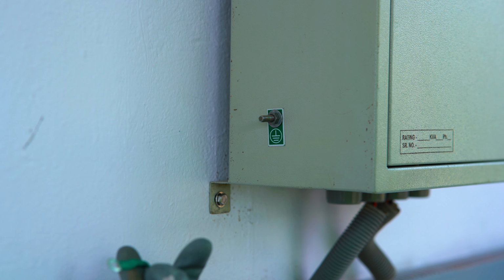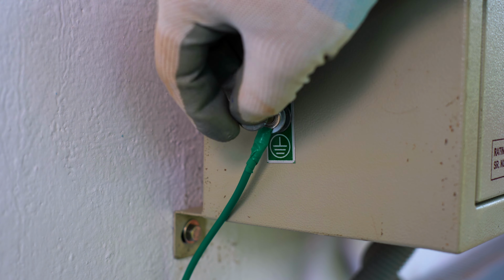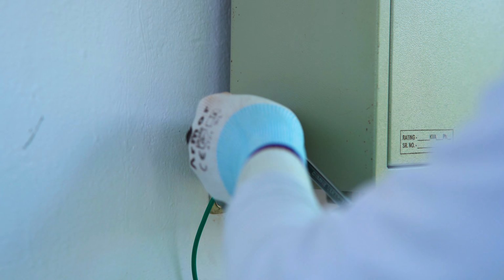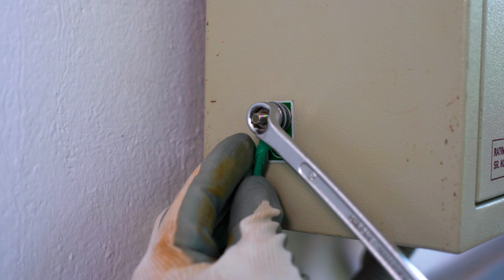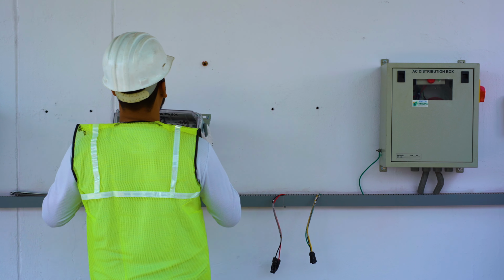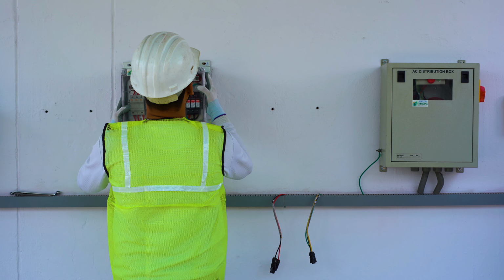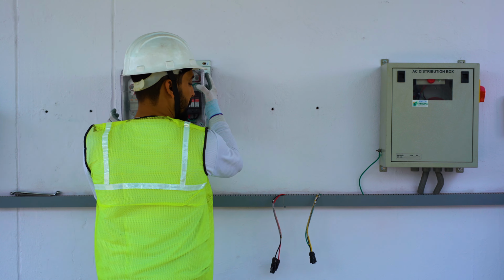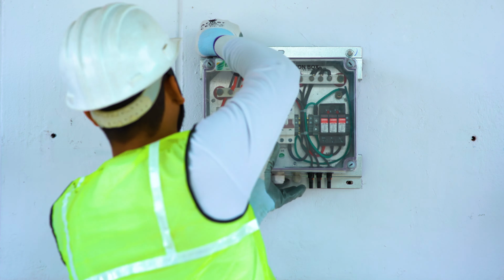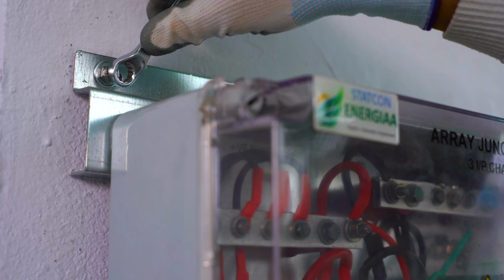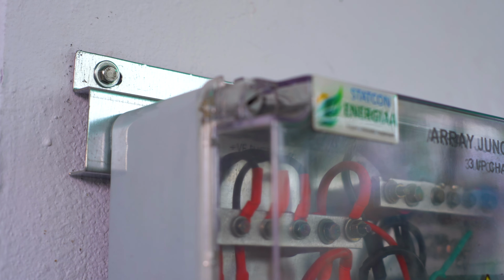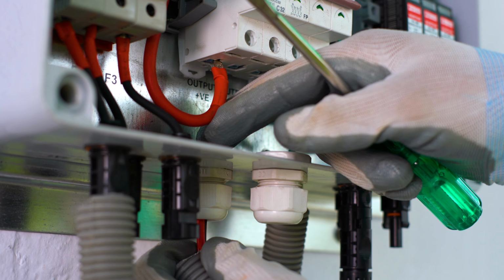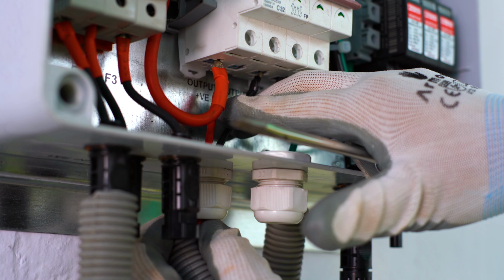Please ensure to connect the earthing point of the AC distribution box. Now we'll mount the DC array junction box on the wall. Make sure that this comes with an SPD or a surge protection device, which is necessary for the protection of your plant. Now we'll connect the DC positive and DC negative wires on the AJB's output.